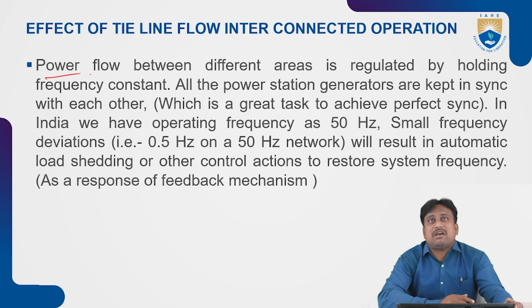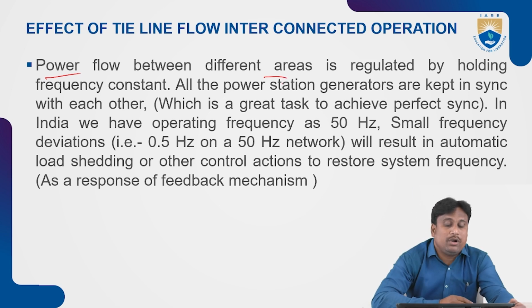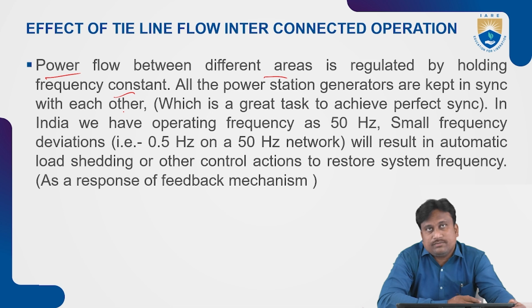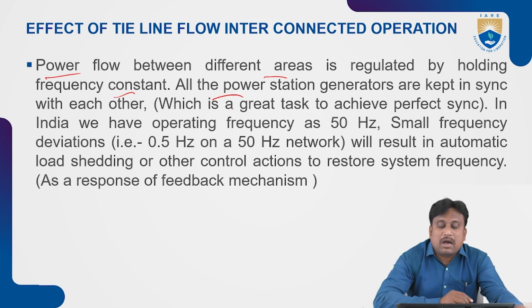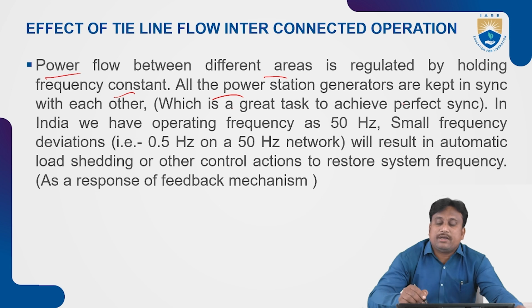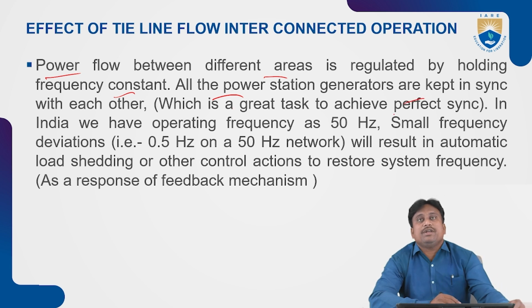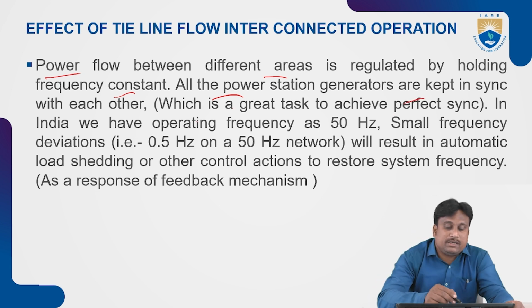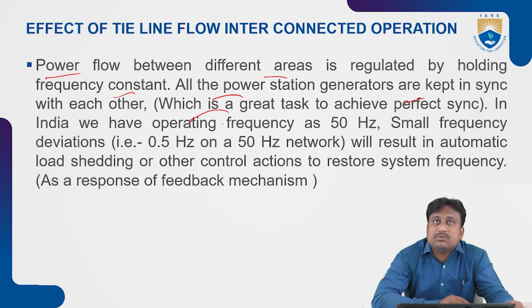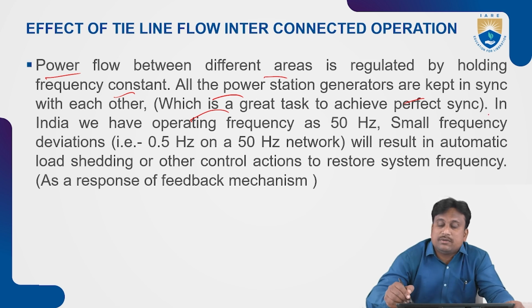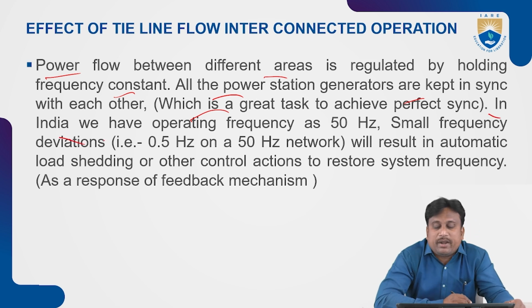So the existence of power flow in between the different areas is regulated by holding the frequency as constant. This we already discussed in the load frequency control. So all the power stations' generators are kept in the synchronous condition with each other. That means, which is a great task, to achieve the perfect synchronizing condition. So in India we have an operating frequency of usually 50 Hz.